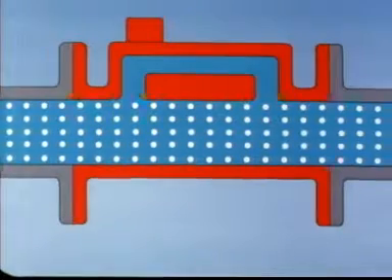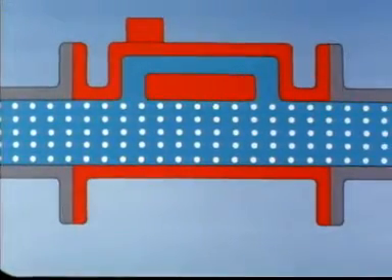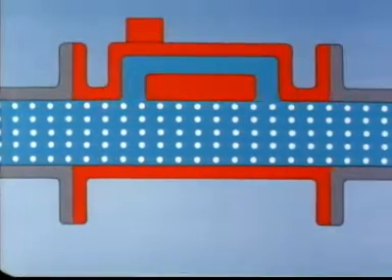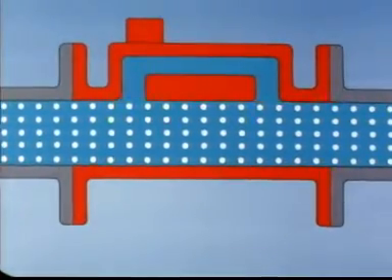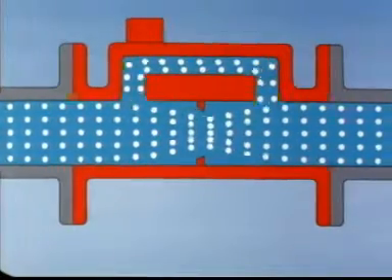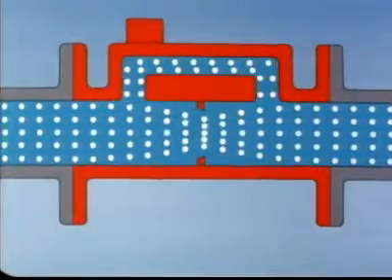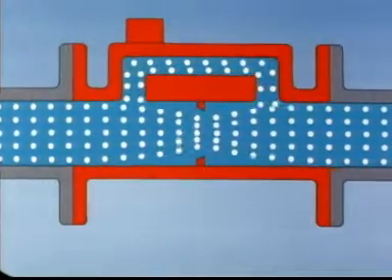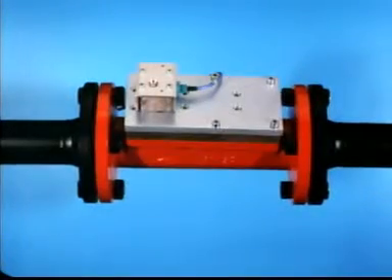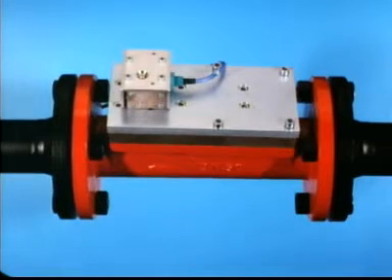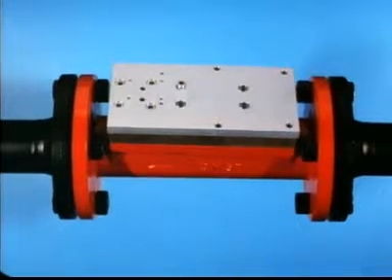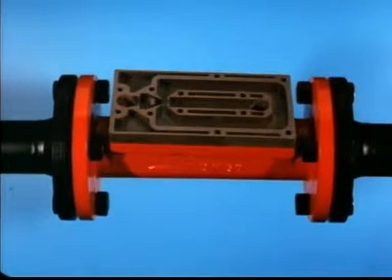The fluidister measures a partial flow which is proportional to the total flow. We obtain the partial flow by arranging a restriction in the main flow path, thus diverting part of the fluid through the fluidister. The sensing head can easily be opened to reveal the ingenious fluidister oscillator, which has no moving parts whatever.